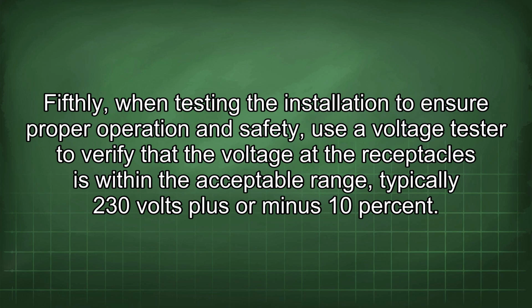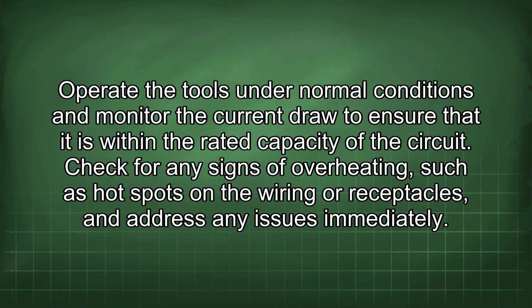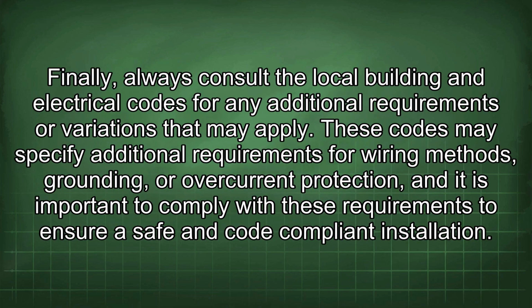Fifthly, when testing the installation to ensure proper operation and safety, use a voltage tester to verify that the voltage at the receptacles is within the acceptable range, typically 230 volts plus or minus 10%. Operate the tools under normal conditions and monitor the current draw to ensure that it is within the rated capacity of the circuit. Check for any signs of overheating, such as hot spots on the wiring or receptacles, and address any issues immediately.